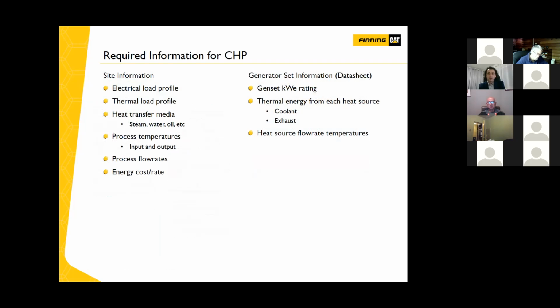From the site information, we need to know the electrical load profile to understand the loads present and size the genset, the thermal load profile to understand what the site will use the heat for, and the media used to transfer the heat—steam, water, or oil, depending on the need. This will definitely affect the design of the heat exchanging equipment. And of course, we need to know the temperature of the site media into the heat exchanger and the desired output temperatures.